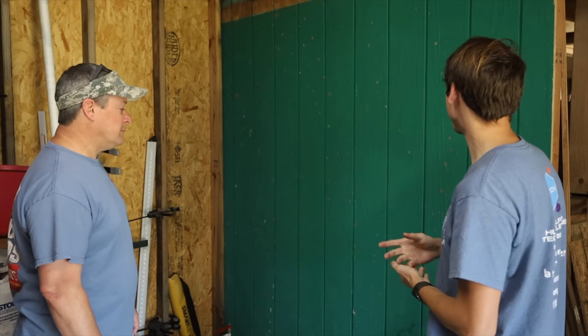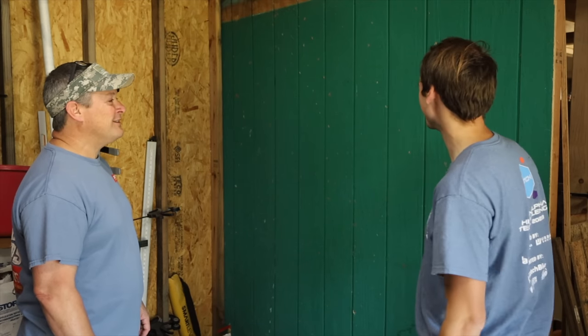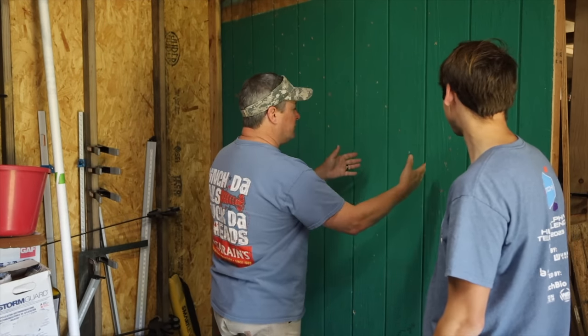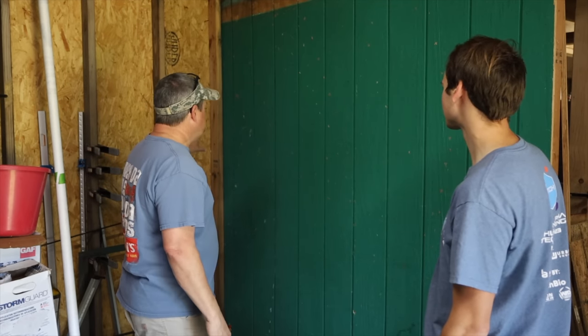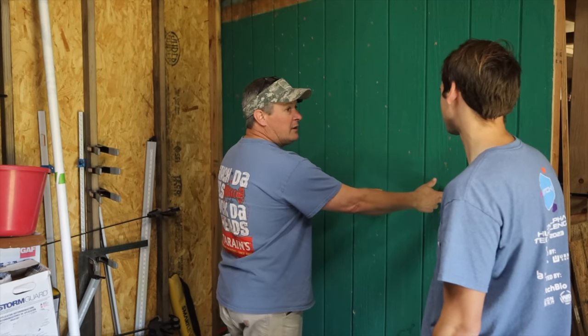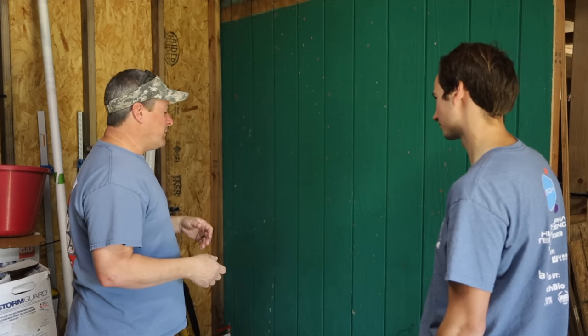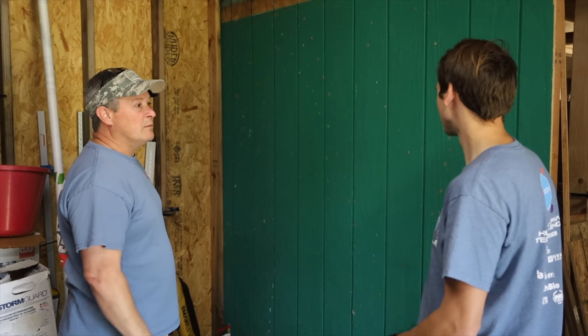This is the addition that we built, and this is the original abandoned shed right here — we just left it how it is. We're thinking about using this wall to put our main breaker panel. So our distribution panel, if we mount it on this wall, it would be a surface mount. You'll end up having to build out some framing and protect the wires coming through. Typically you'd run it either in conduit, placed in the stud cavity wall itself, and come into the panel. Or if you're going to leave this exposed, run it in conduit from the disconnect to the panel. All your home runs would be coming out of the top or bottom or side of the panel, depending on where they're going.